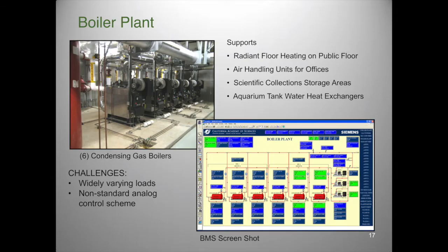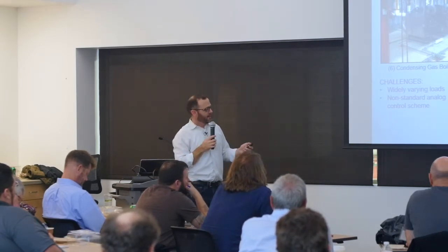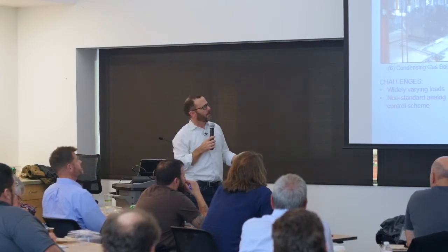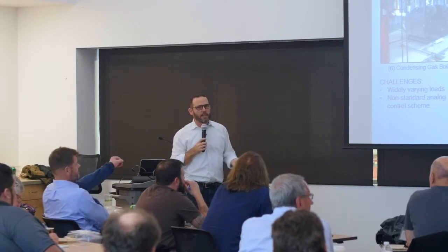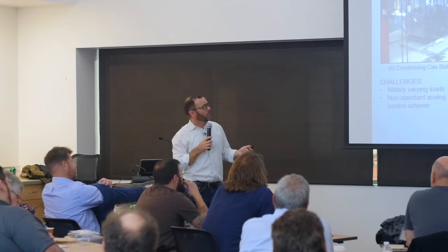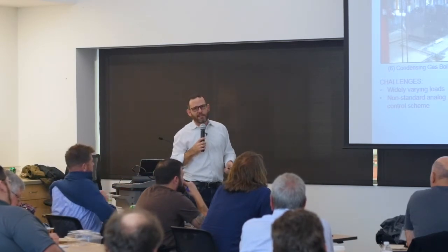Okay, so boiler plant, this is really interesting, and this is what I wanted to share some talk about. The chiller plants, there's maybe five chiller companies, something like that. There's like 1,000 boiler companies, and they're all different, and they all have their own special way that they control their boilers, and so these things were up and running and ran into some early commissioning issues.